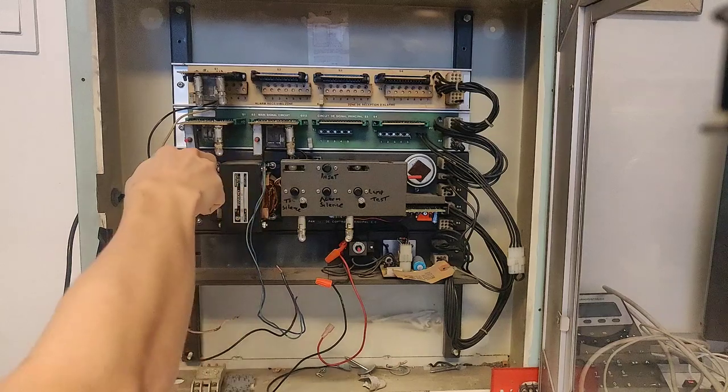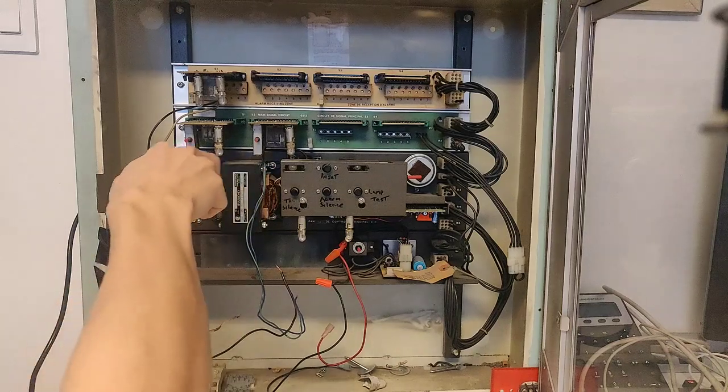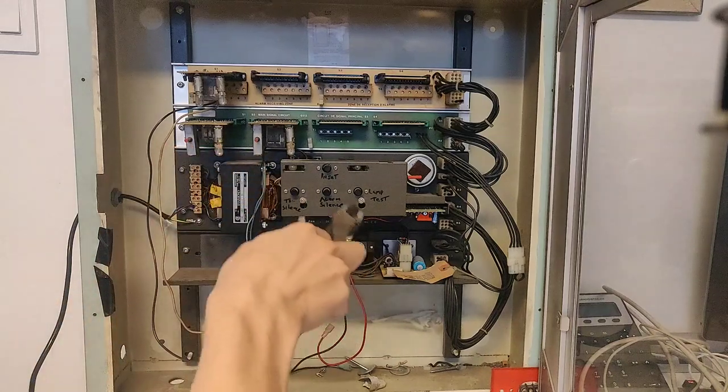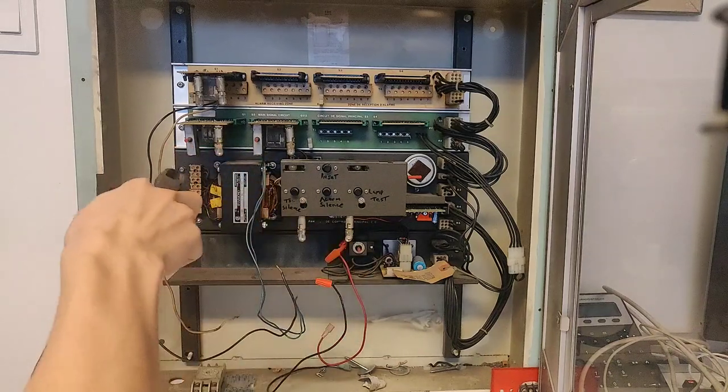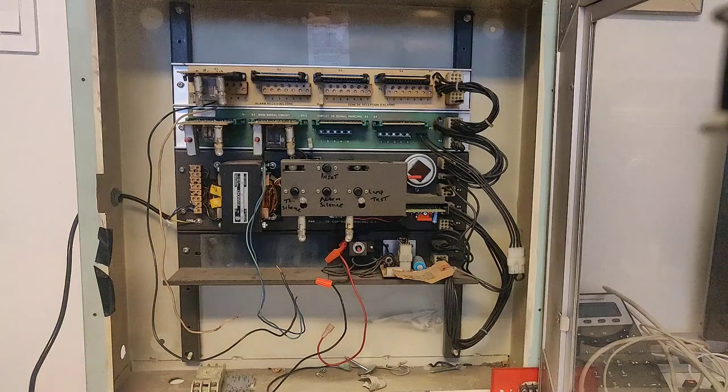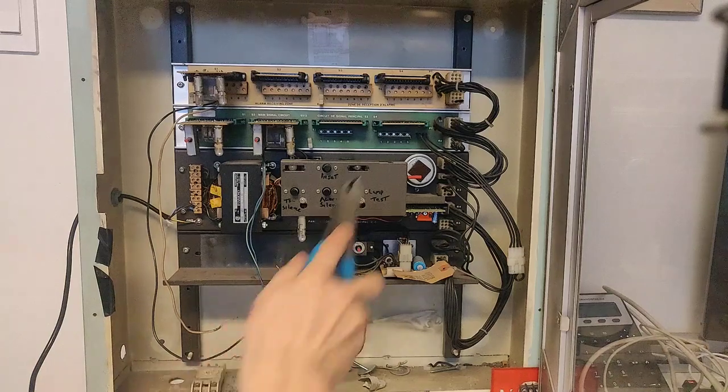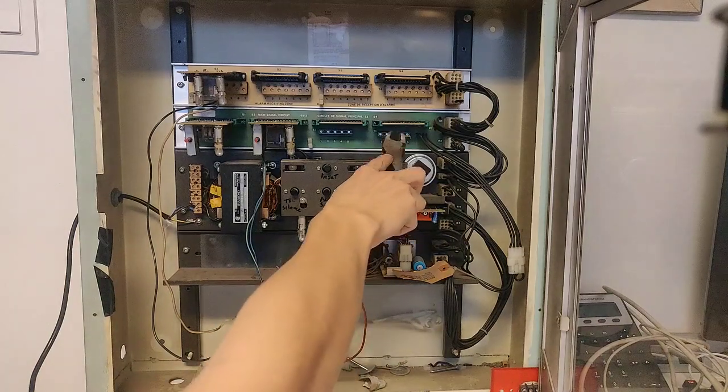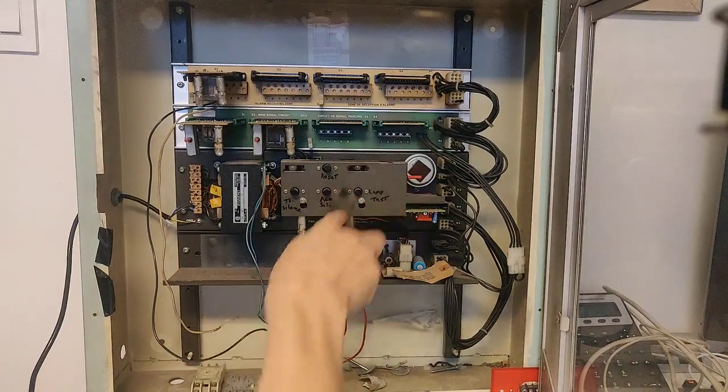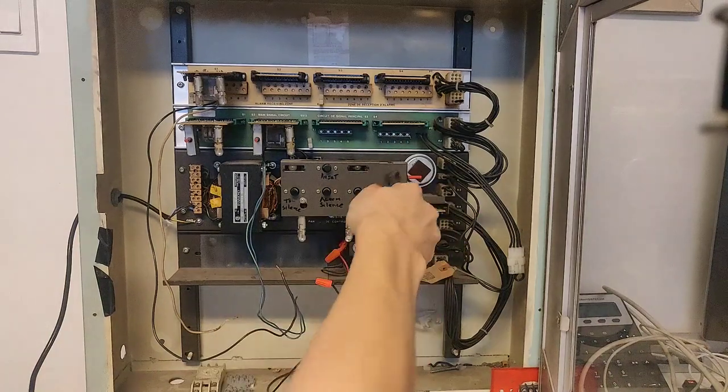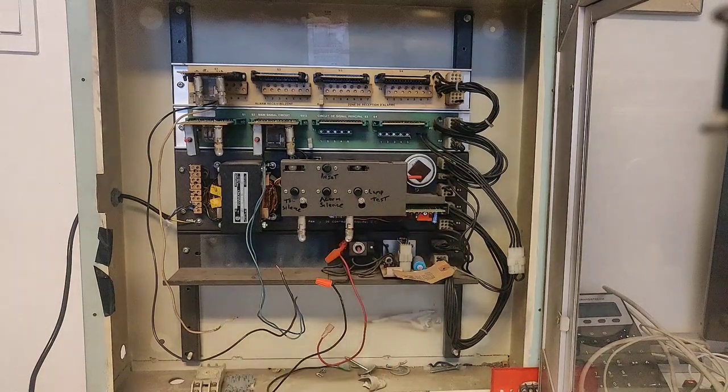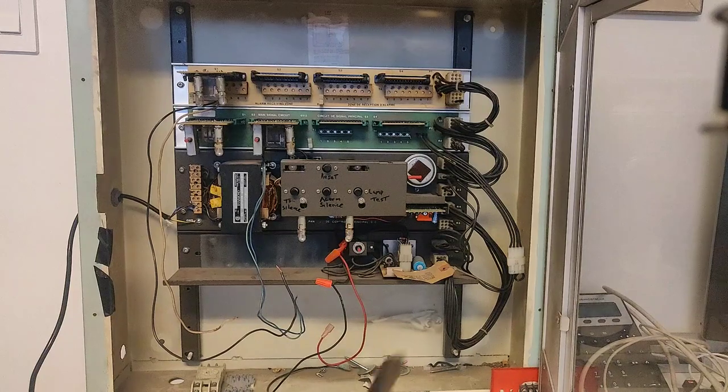These are the circuit breakers for the alarm circuit. These circuit breakers are horrid—they go bad all the time. So a lot of times if you just give it a good tap and then reset it, you'll be back to normal.